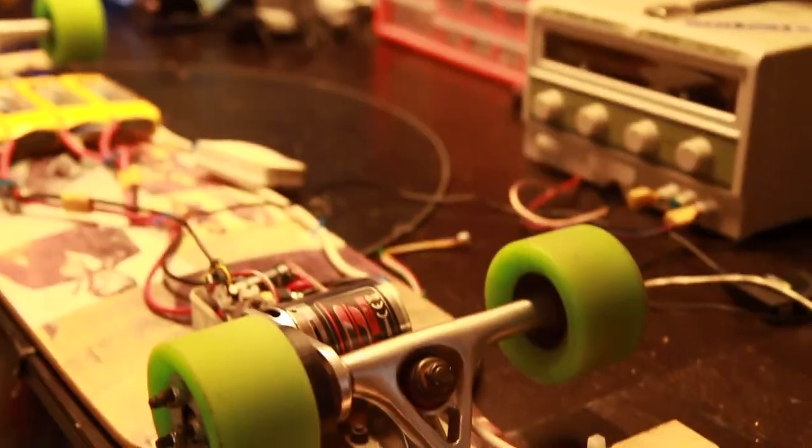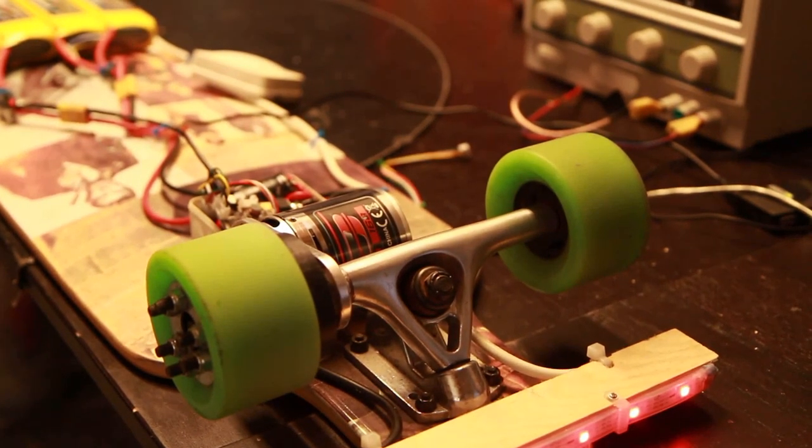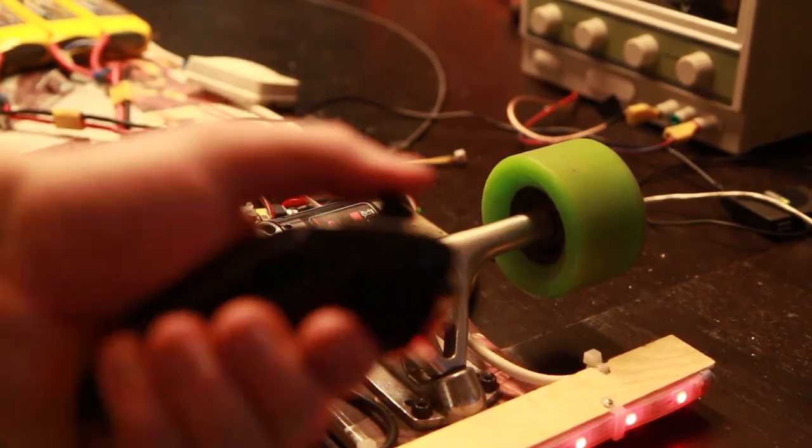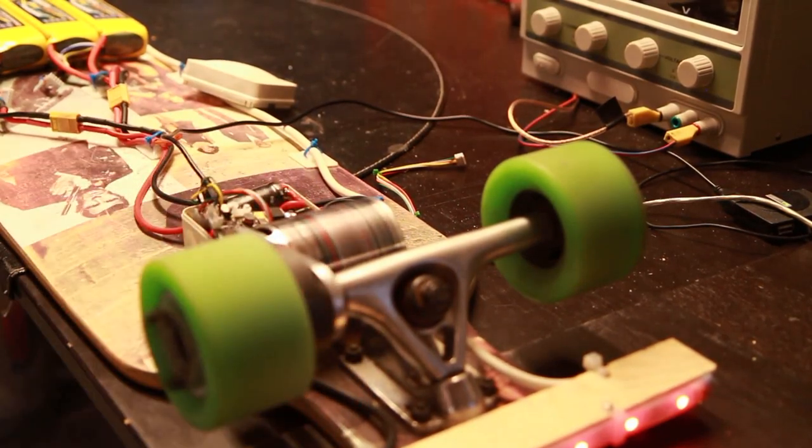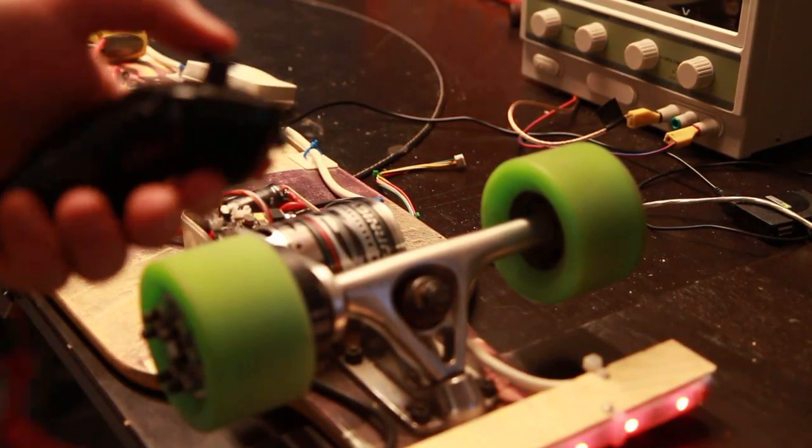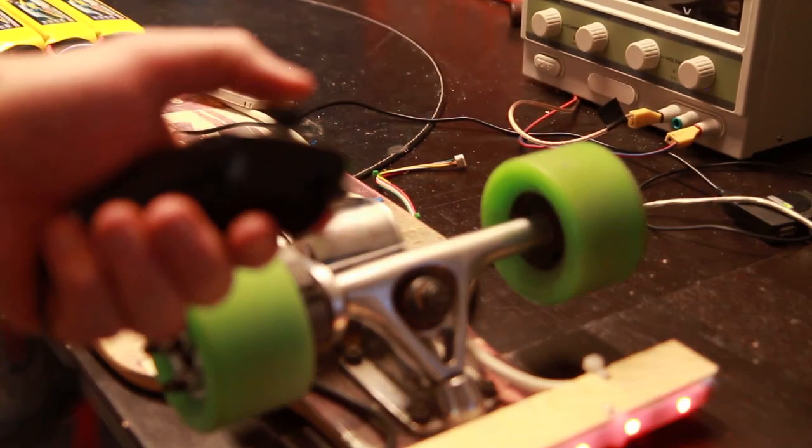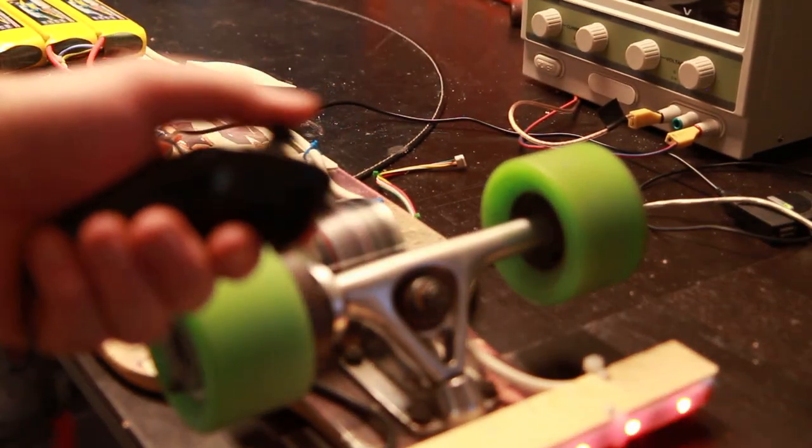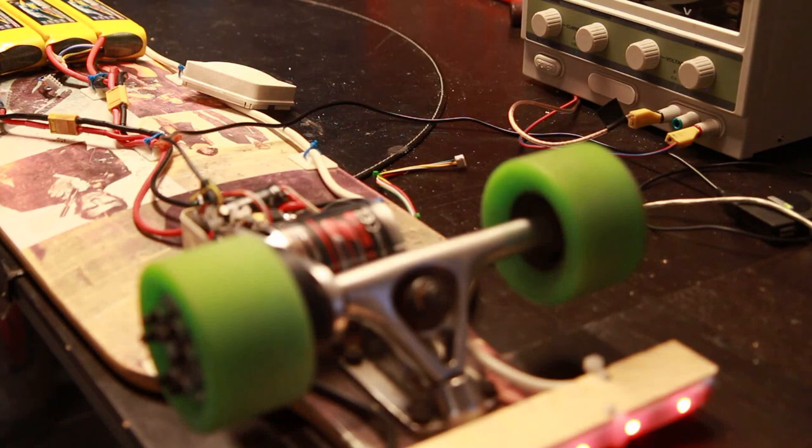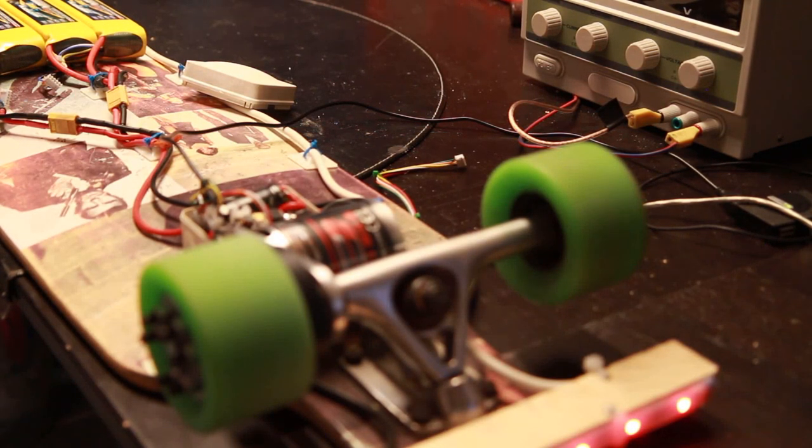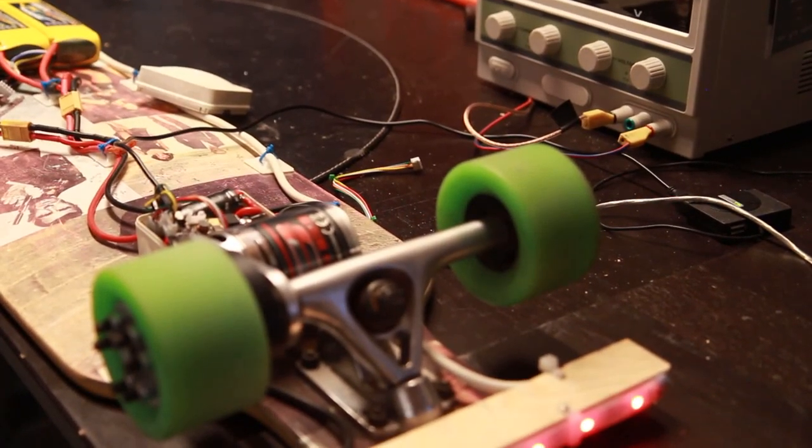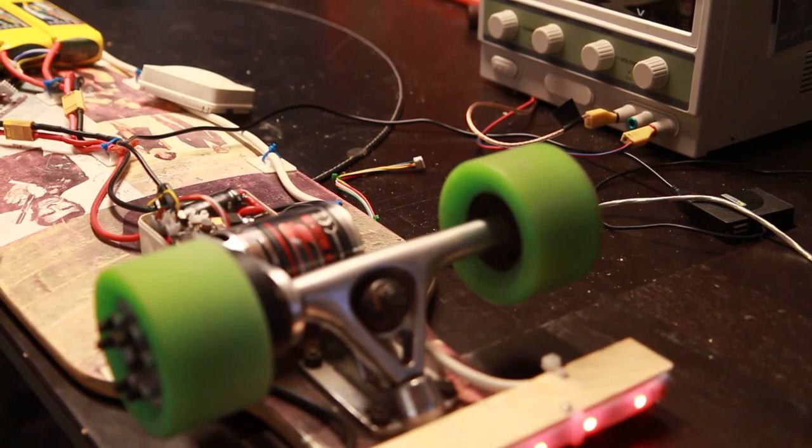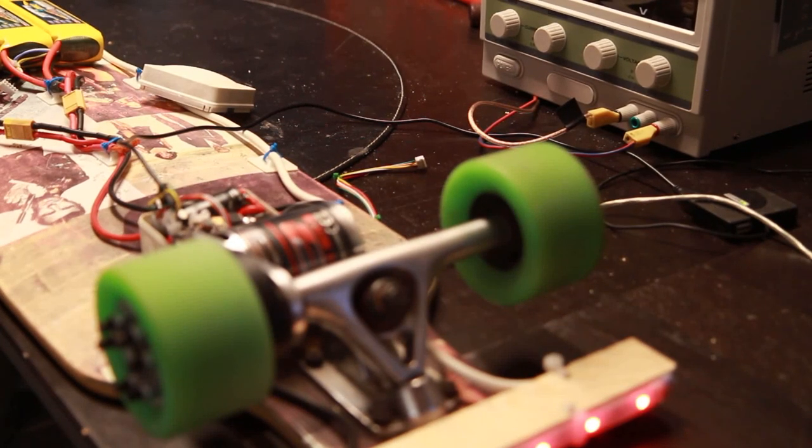Write the configuration. If we go back to have a look at the motor now, you can see that it's a lot slower. The reaction is delayed, both with and without braking. But having it at two seconds is quite a lot too slow. What feels natural for me is having the positive limit at half a second and the negative one at 0.2 seconds.